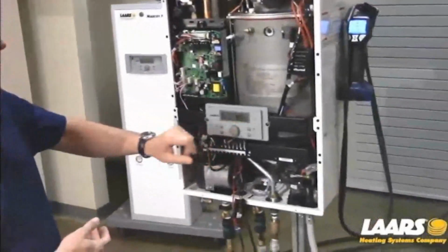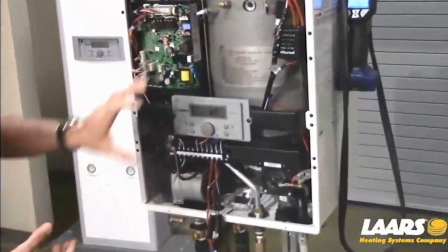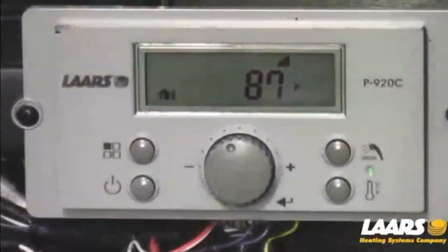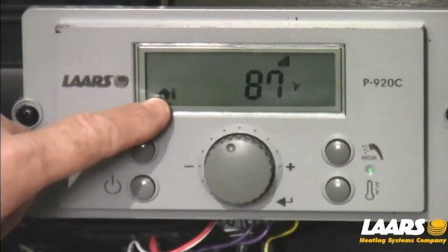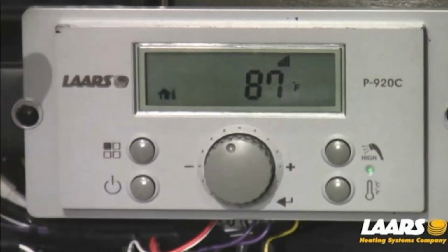Now we're registering 87 degrees. That's the tank temperature, or the heat exchanger temperature. We haven't been running this very long. Outdoor sensor's disconnected, and the outdoor sensor symbol is flashing. That means that that sensor is disconnected. I'm going to give the boiler a call for heat.